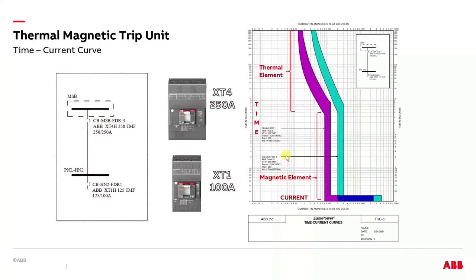Here's some curves just so you can see the response of it. Some of you may not be familiar with the time current curves, but essentially all it is, it's a graph that shows you at what amperage and what time a circuit breaker is expected to trip. And these bars, this big purple, that's one circuit breaker. The blue, it's another circuit breaker.